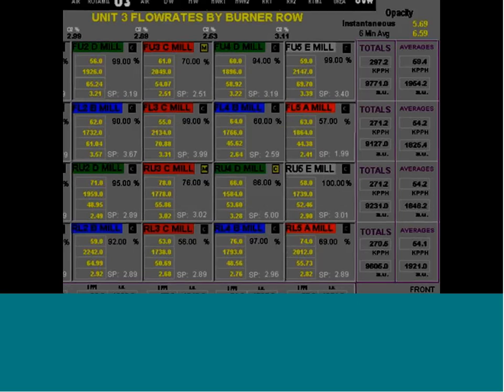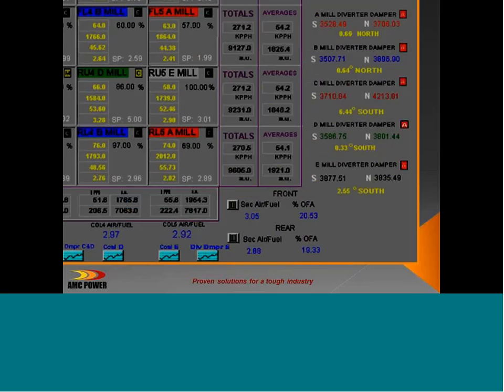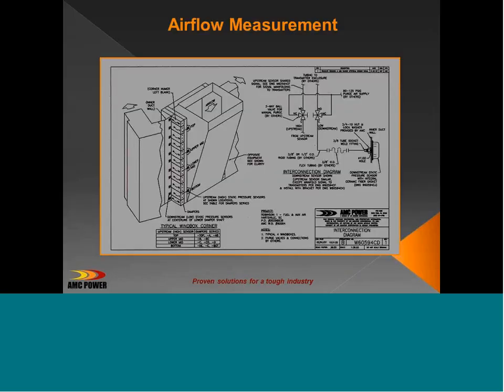And on T-fired units, we do something very similar. But again, instead of using the pitot tube technology, we use static pressure measurement across each damper: aux air, fuel air, aux air, fuel air. So we measure the static pressure, and we convert that, again, using our wind tunnel out in Santa Rosa, California. We're able to develop curves that help us convert damper position and static pressure into a flow across each damper.